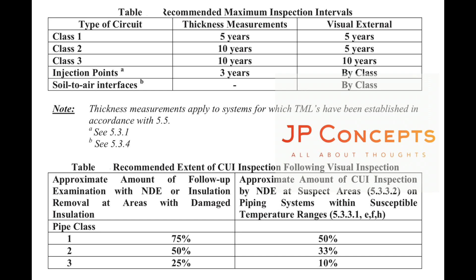Next, the recommended extent of corrosion under insulation inspection following visual inspection. In this table you can see the percentage of the extent of insulation to be removed for inspection and the percentage of area to be covered through proper NDE techniques. Here is the extent of visual external and corrosion under insulation inspection. External visual inspection, including inspections for corrosion under insulation, should be conducted at the maximum intervals listed in the previous table that I showed. Alternatively, external visual inspection intervals can be established by using a valid RBI assessment conducted in accordance with API 580. This external visual inspection on bare pipe is to assess the condition of paint and coating damages.